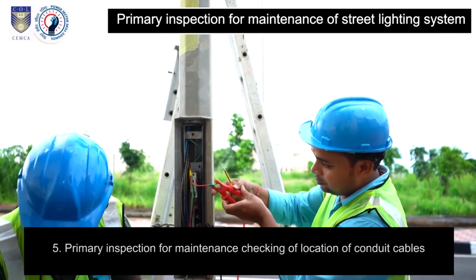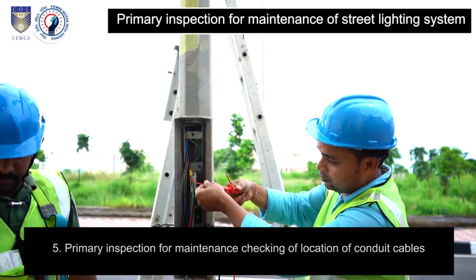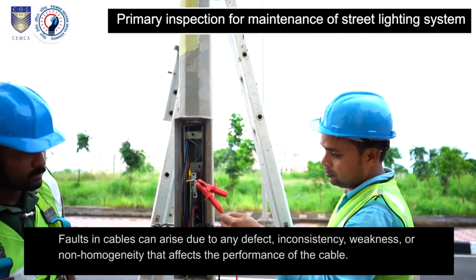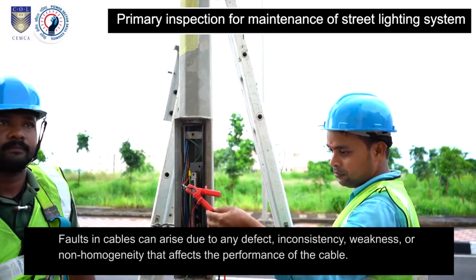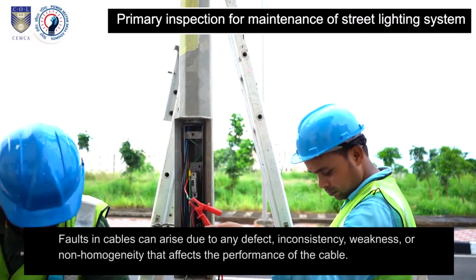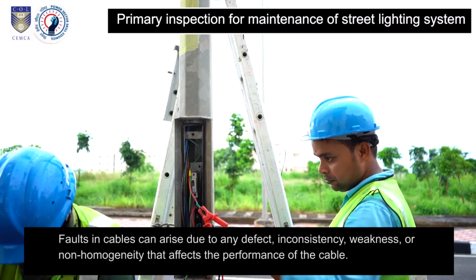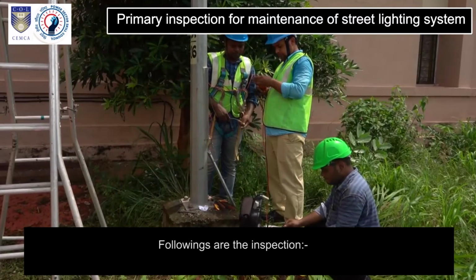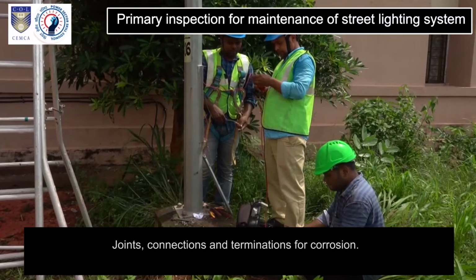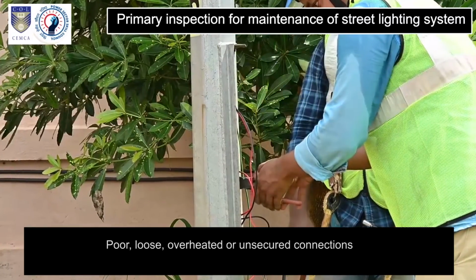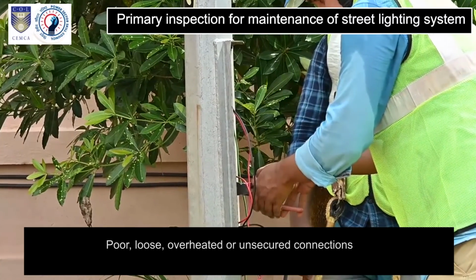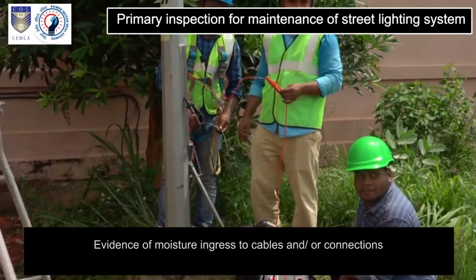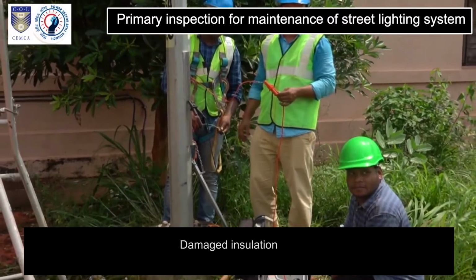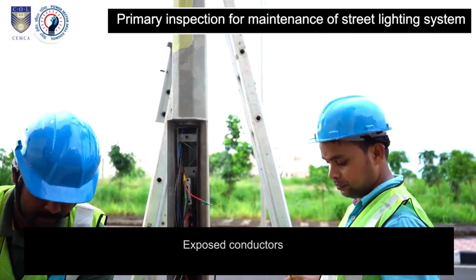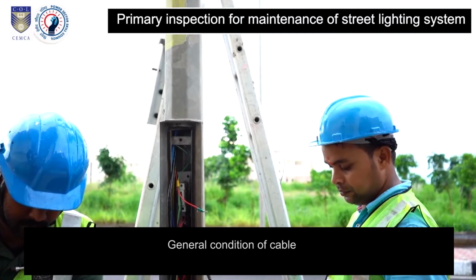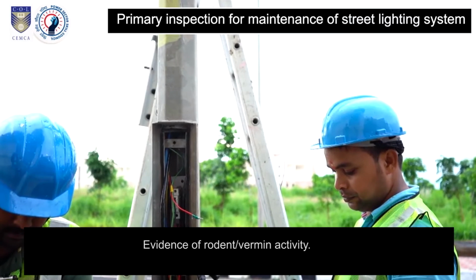5. Primary inspection for maintenance: checking of location of conduit cables. Faults in cables can arise due to any defect, inconsistency, weakness, or non-homogeneity that affects the performance of the cable. Following are the inspection items: joints, connections, and terminations for corrosion. Poor, loose, overheated, or unsecured connections. Evidence of moisture ingress to cables and or connections. Damaged insulation. Exposed conductors. General condition of cable. Evidence of rodent, vermin activity.